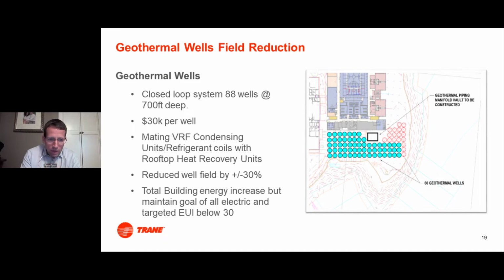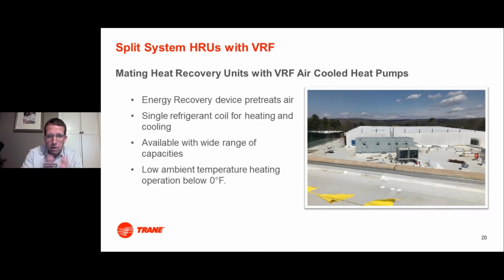They were looking at ways to reduce first cost, but not take too much of a hit on their annual energy usage. So one thing that we thought about and that the VRF system allowed us to do was reduce the geothermal well field by 30% by mating VRF condensing units with rooftop energy recovery units that served every space in the building. Now the total building energy did increase, but we were still able to maintain an EUI below 30, which we thought was pretty good.